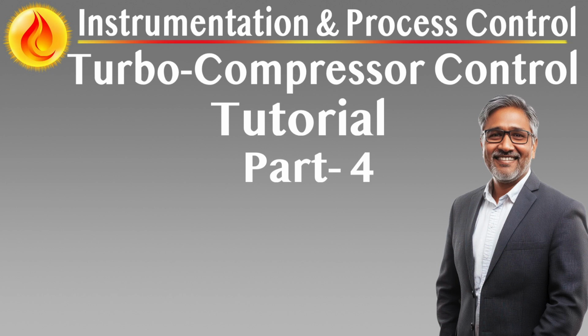Fire and gas detection and suppression, integrated safety layer for early hazard detection and automatic response within turbine enclosures. Safety system overview. The Turbo Compressor Control System, TCCS, includes a fully integrated fire and gas, F&G, detection and suppression subsystem to protect the turbine enclosure and adjacent process areas from combustion-related hazards, designed in accordance with international standards such as NFPA 72, NFPA 750, and NFPA 12.